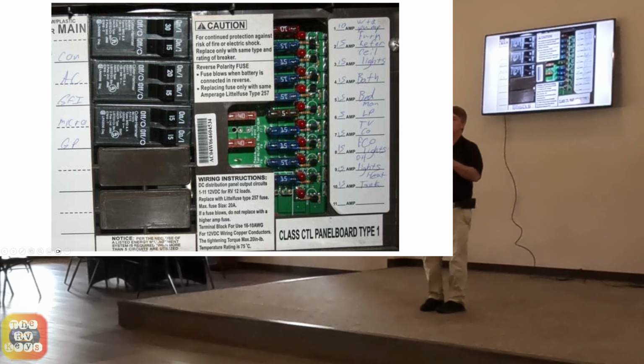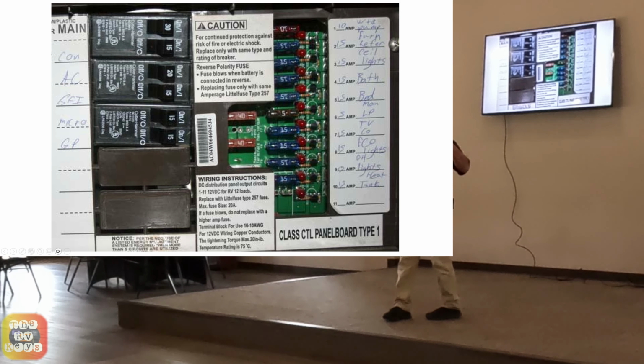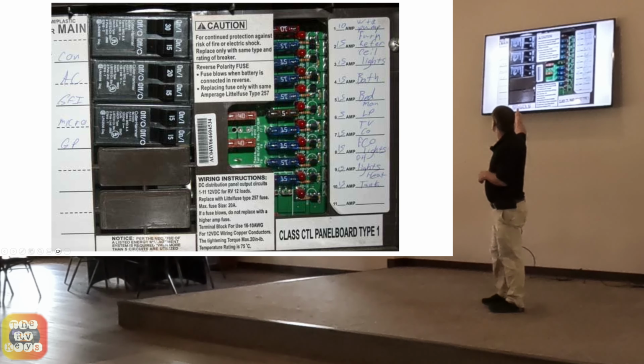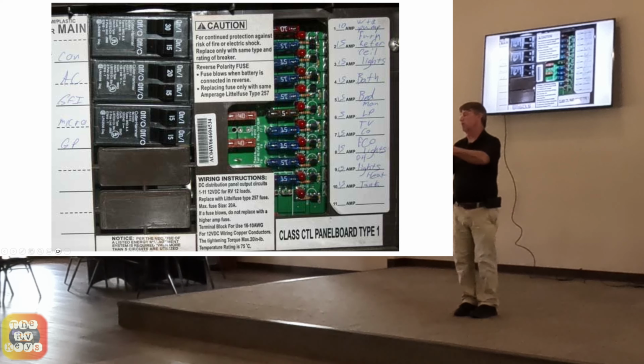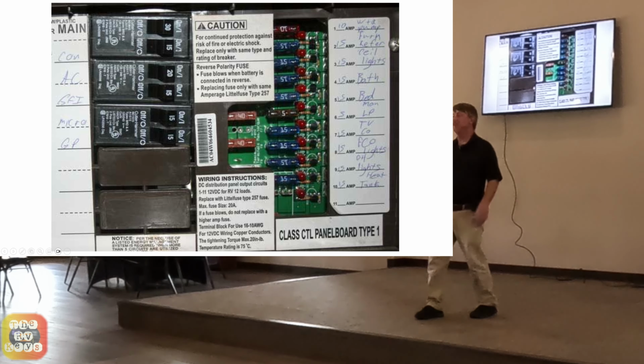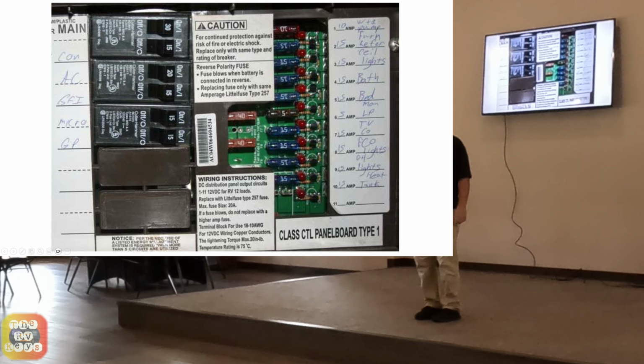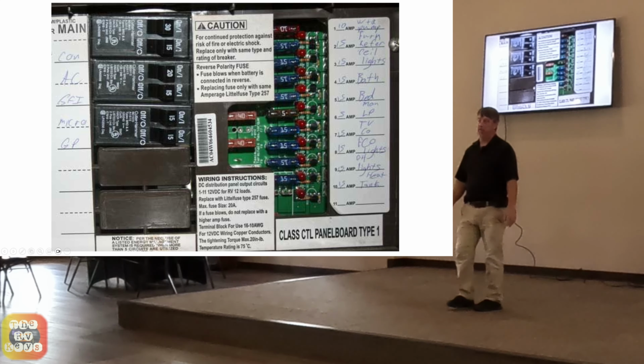Take out the fuse, use a meter, and check it. If you don't know how to use a digital multimeter, a lot of people wouldn't even get near that panel, and that's fine, this is a point about electrical safety. But if you feel comfortable, use needle nose pliers or your fingertips on the right side, pull the fuse out, and check it with a meter. Once you prove the fuse is good, put it back in. One caveat, a fuse can check fine but still fail under load. If things don't make sense, it's worthwhile to take a known good fuse out of a packet and swap it in to see if that solves the problem.